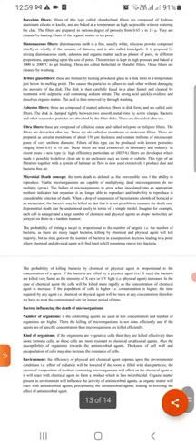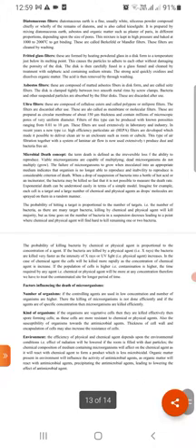Fritted glass filters are filters formed by heating powdered glass in disc form to a temperature just below the melting point. This causes the particles to adhere to each other without damaging the porosity of the disc. The disc is then carefully fused with the glass funnel and cleaned by treatment with sulfuric acid containing sodium nitrate. The strong acid quickly oxidizes and dissolves the organic matter. The acid is then removed by thorough washing.